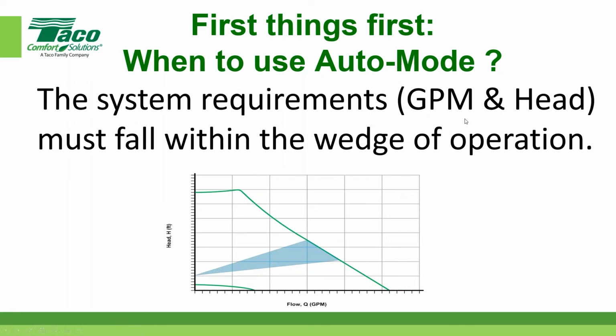They forget this simple thing: when the manufacturer shows you this little wedge, this shaded in area, what they're saying is that's the only place the pump's going to operate. So if all of a sudden you have a requirement to be here under your design load condition, the last thing you want to do is leave it in the adaptable auto mode. Hopefully that makes sense to you?